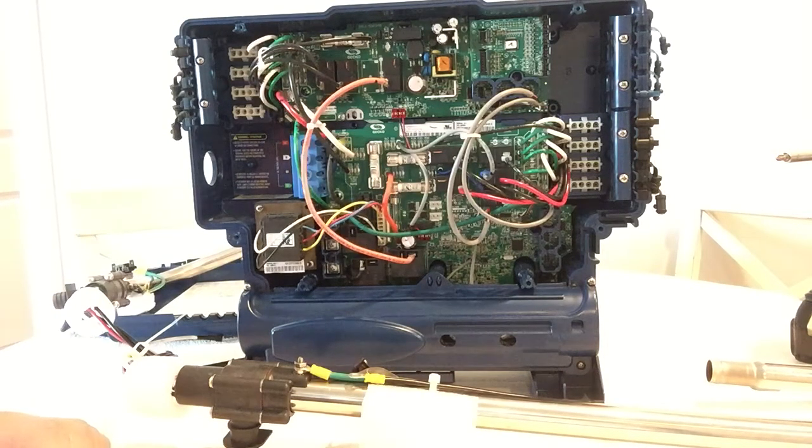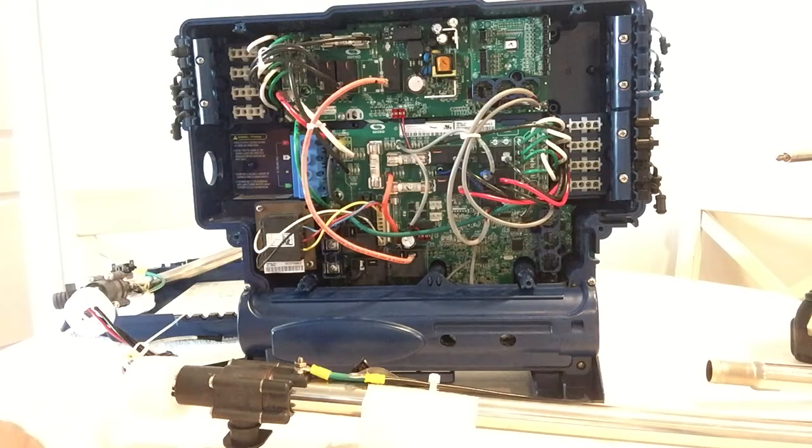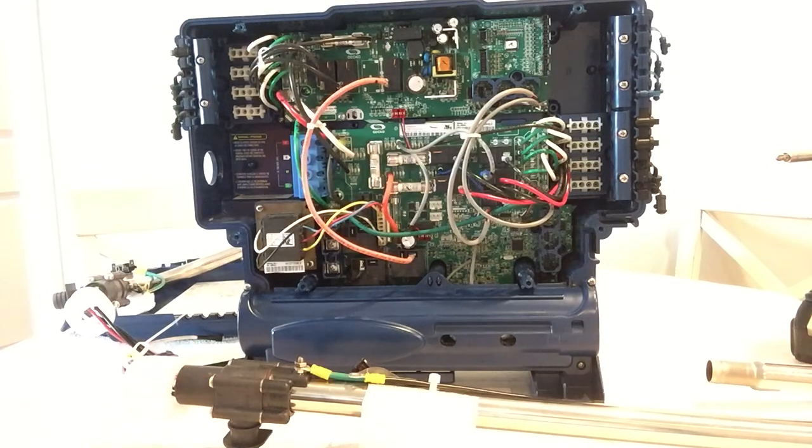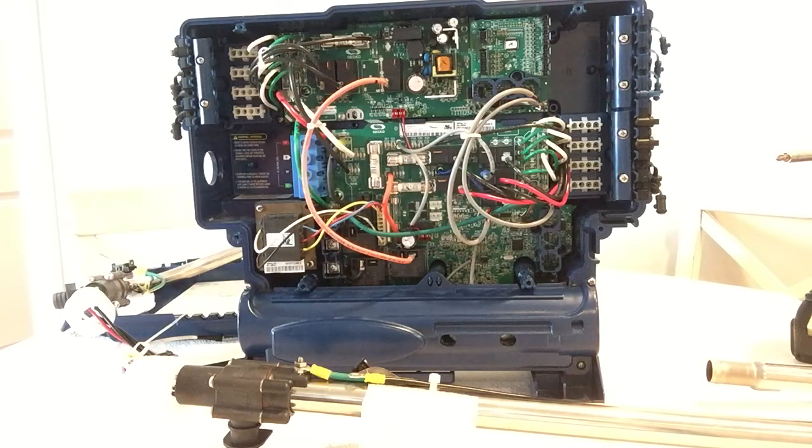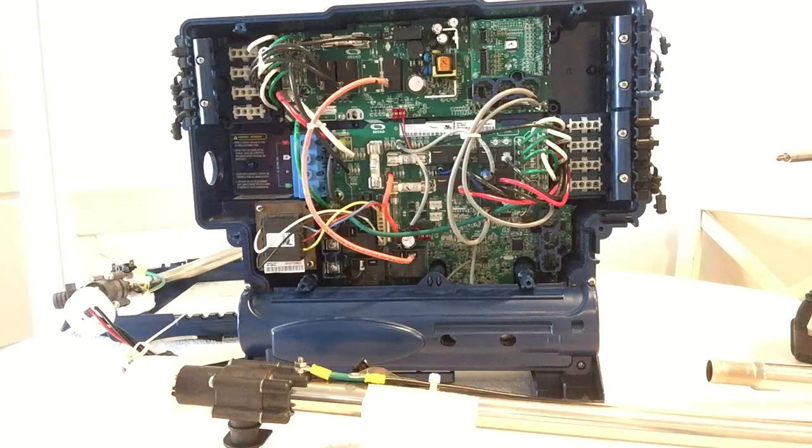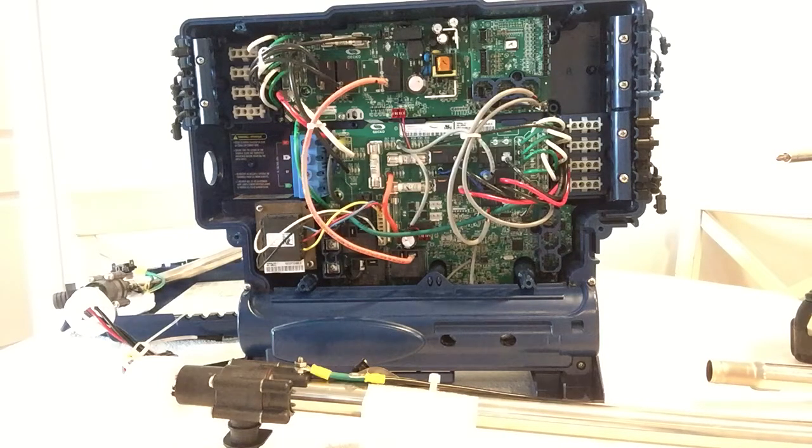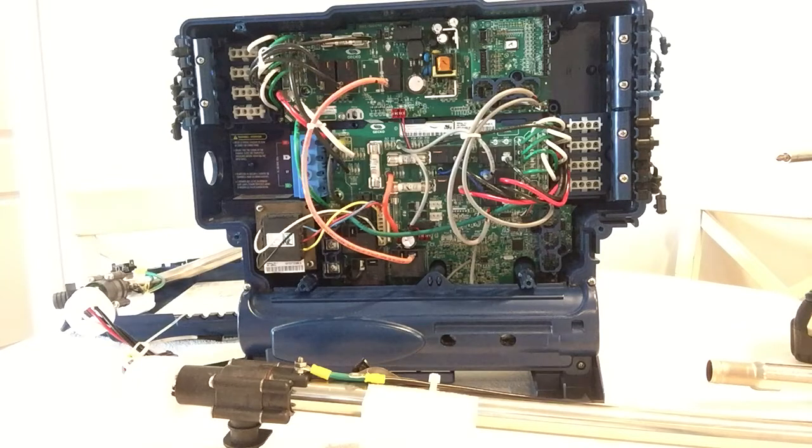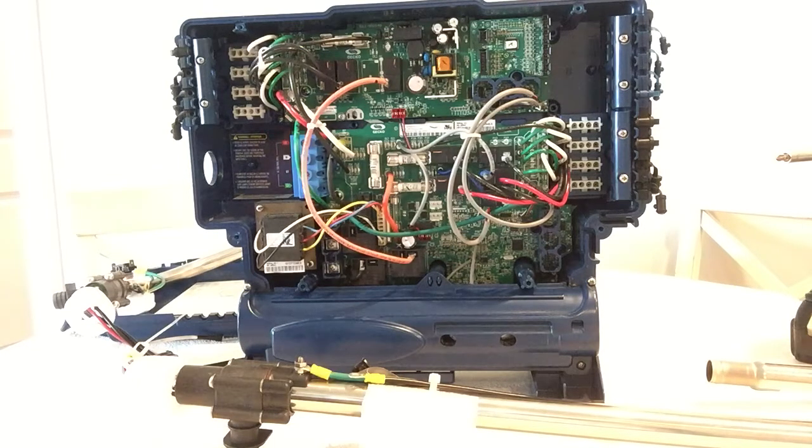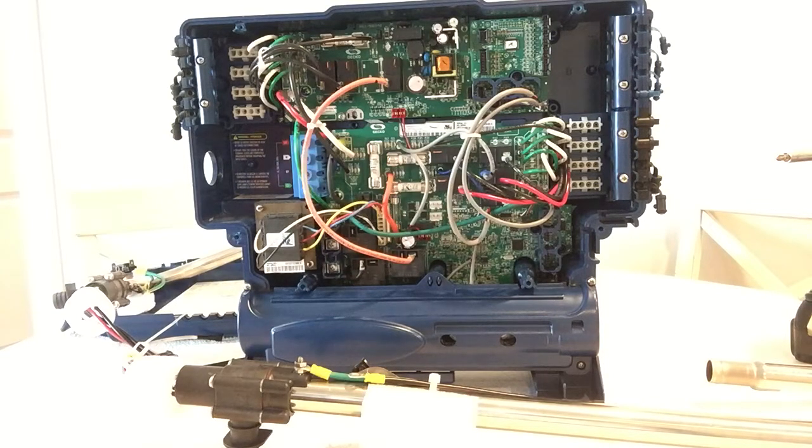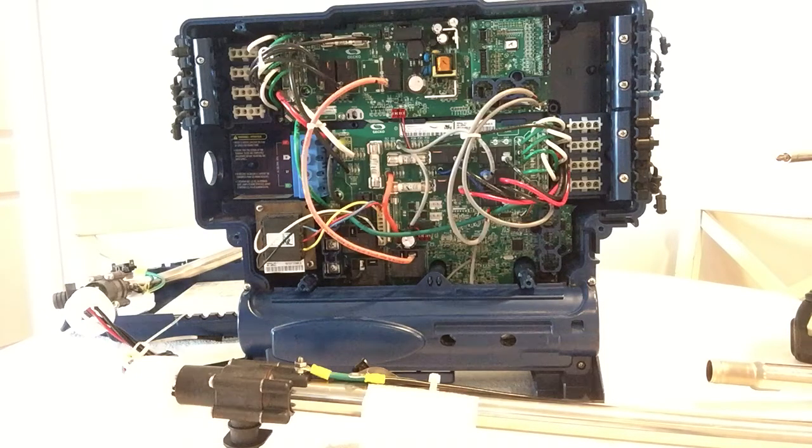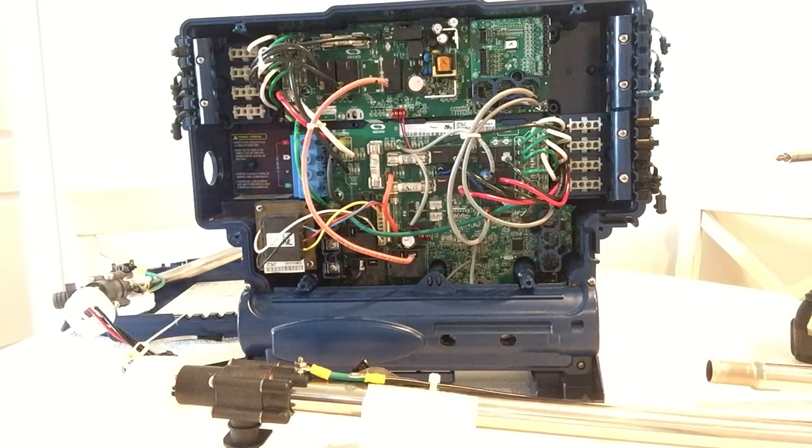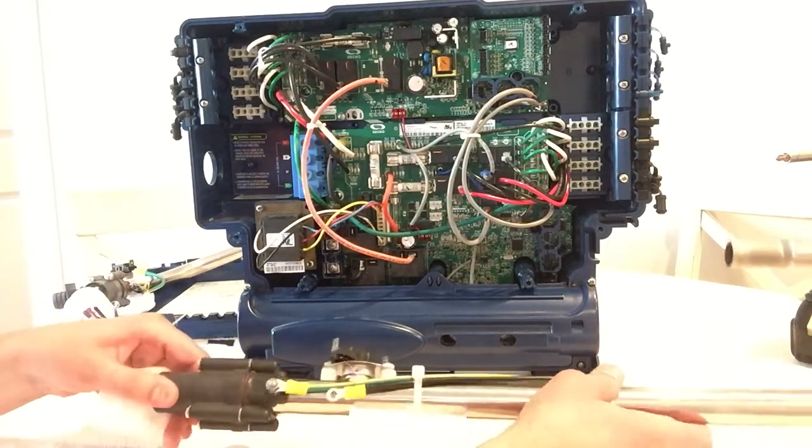So it could trip when there's a problem and it could trip when there's no problem at all. Usually what happens when you notice something like this is your screen will say heating to whatever temperature you have it set at, heating to 102, heating to 104, whatever, and the spa does not heat at all. You take your voltmeter and you check power to the heater and you're getting voltage to the heater, but it's still not heating. So the TCO switch is the reason for this.